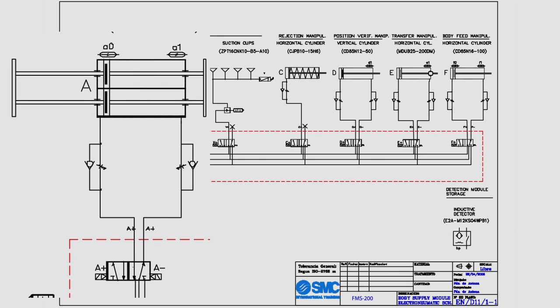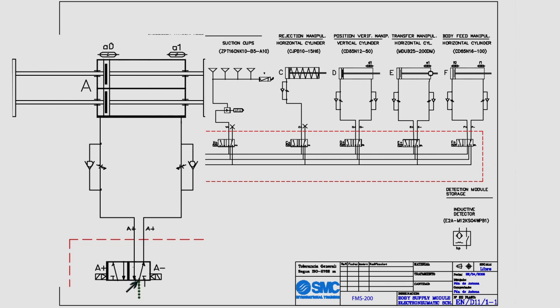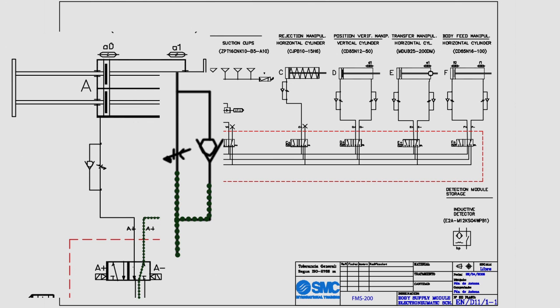If we look at the valve we can see that it has two boxes. Those two boxes mean that it only has two positions, so it's either going to be in one or the other position. If we follow the valving right now in the air supply coming in, we can see that we have pressure coming here from our FRL. It goes up and goes through this port which is connected right here. It goes through the valve and then goes on through what is known as a metering device right here. This is a flow control that allows us to meter the amount of air in or out.